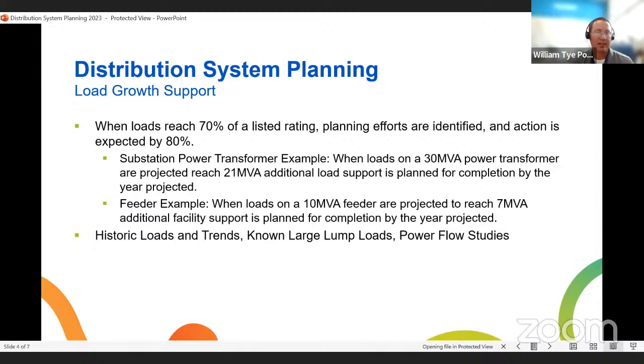One example would be our substation power transformer: when loads on a 30 MVA power transformer are projected to reach 21 MVA of additional load, support is planned for completion by that projected year. So if we're projected to reach 21 MVA within 3 years, we have plans to have that particular project completed by that timeline. Of course, a lot of things tend to happen and projects are delayed, so we have this 10% buffer room for getting the projects completed by the time we reach that 80% mark.